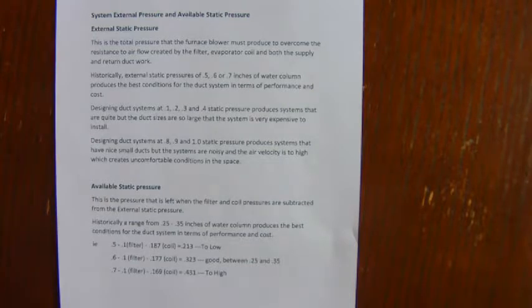Historically, external static pressures of 0.5, 0.6, and 0.7 proved to be the best in providing a very good balance between duct system performance as well as cost efficiency for installing the ductwork. Systems that are designed below 0.5, so 0.1, 0.2, 0.3, and 0.4, are typically very quiet.